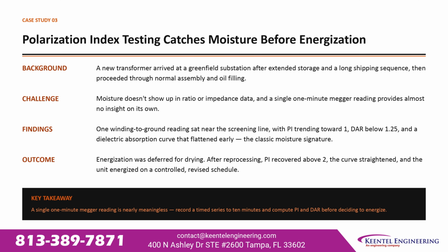A new transformer arrived at a greenfield substation after extended storage and a long shipping sequence, then proceeded through normal assembly and oil filling. The challenge: moisture doesn't show up in ratio or impedance data, and a single 1-minute Megger reading provides almost no insight on its own.